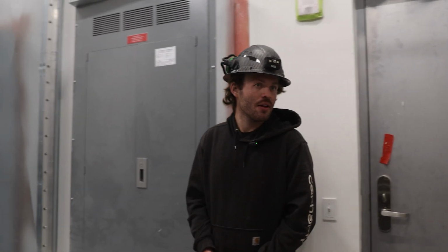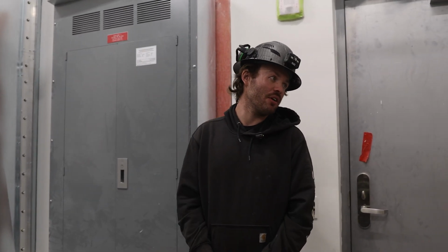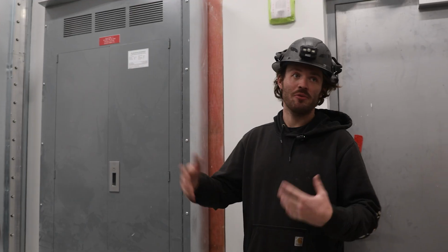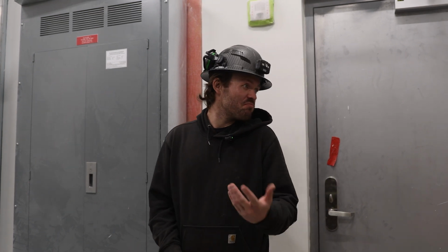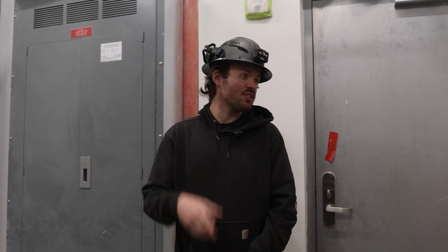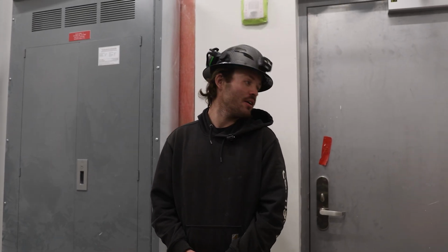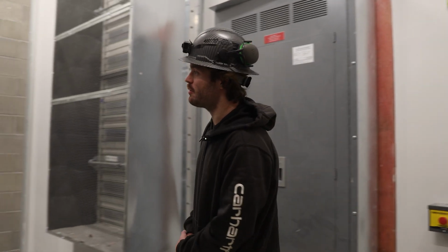It's an emergency generator. We need it to run. There's shutdowns that will stop function of it, but something like that, it's going to still try to run. It will overheat if none of the louvers open, because it's just going to be recirculating hot air. Won't take too terribly long, but it's going to try to run. Part of it, yeah, it's nice to have stairway lighting, nice to have elevator, but it does the fire pump here, right? So if there's a fire, they cut off power, we kind of need this to run.